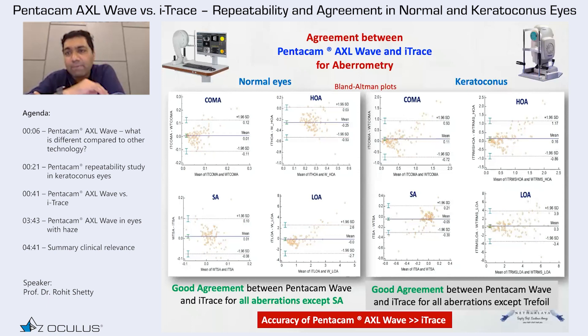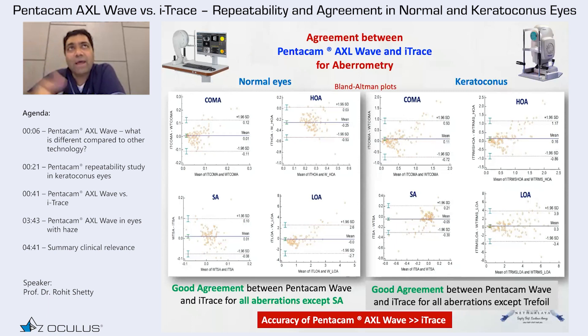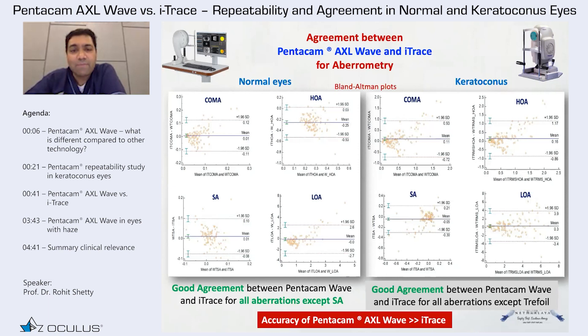We also looked at the impact of tear optics on repeatability. The analysis is still ongoing so I haven't added it here. It's very interesting — when you have a Placido-based system and ray tracing aberrometers with fewer spots, you do have a lot of variation because of tear film, which was not seen with WAVE. This is a very interesting finding, especially now when many people have ocular surface issues.